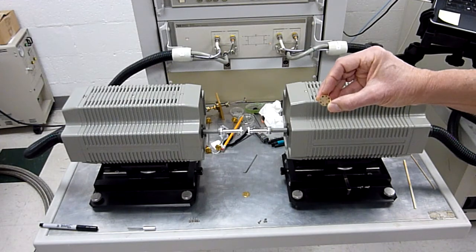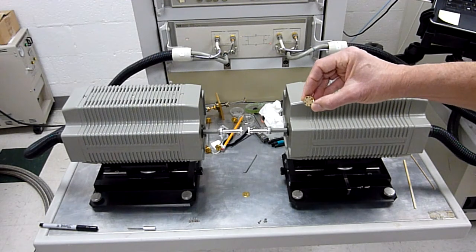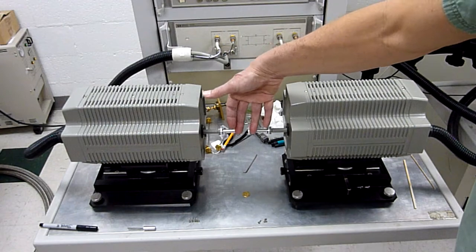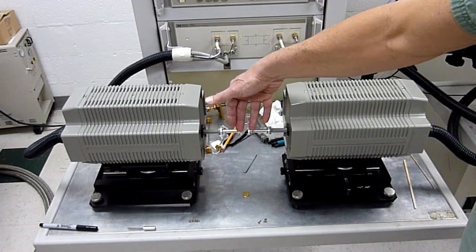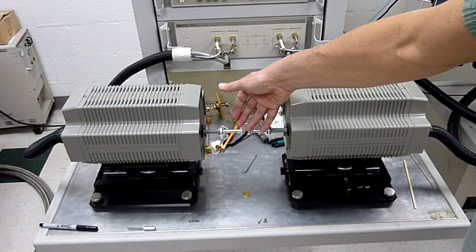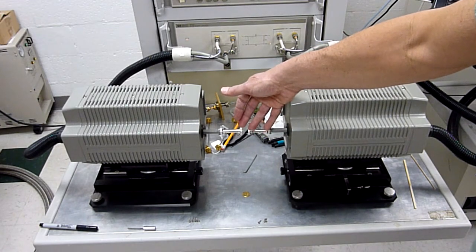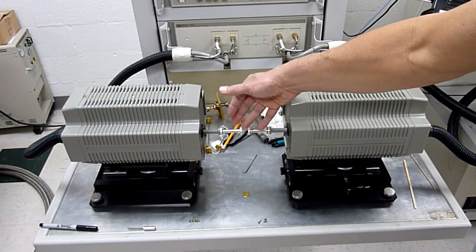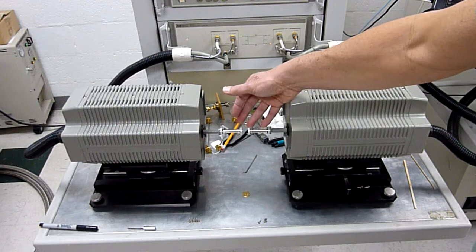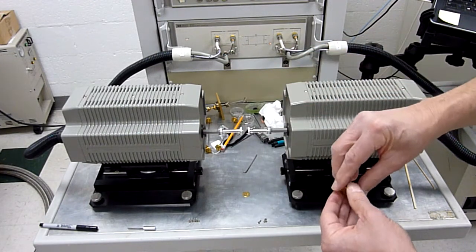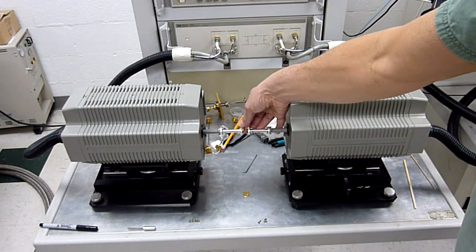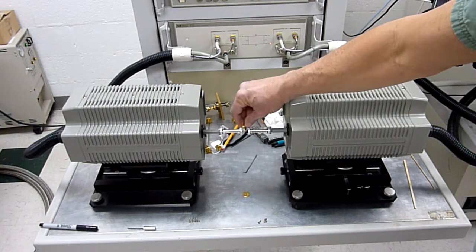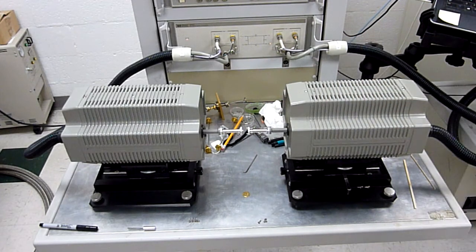It was something of a short, but it was also something of a structure where you had fingers of metal projecting down in and actually back into the waveguide. So you had some potentially resonant lossy structure that was being created rather than a perfect short circuit right at the measurement plane. So we were doing a very flawed calibration.